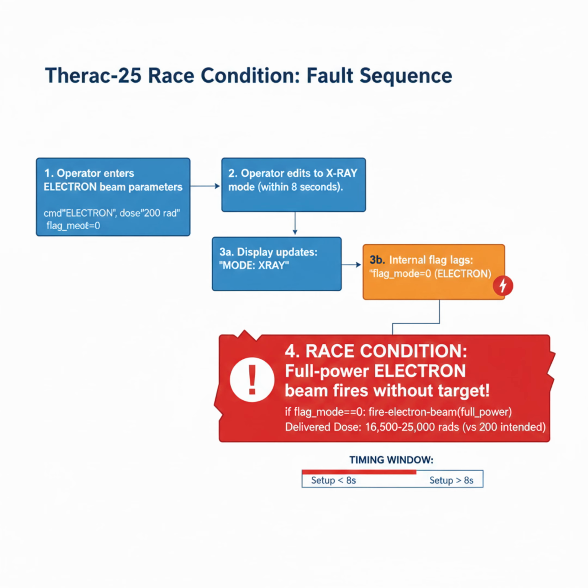When the operator pressed the beam on button, the Therac-25 fired the full power electron beam directly at the patient, without the tungsten target to convert it to X-rays, without the scattering and flattening components to spread it safely. The result was a concentrated dose of radiation. Estimates ranged from 16,500 to 25,000 rads, compared to the intended 200. It happened in less than a second.